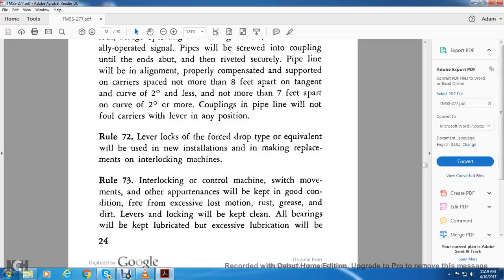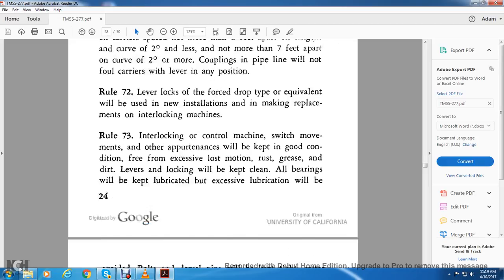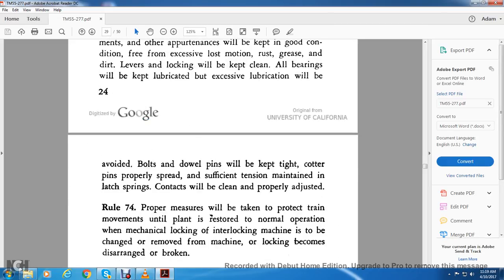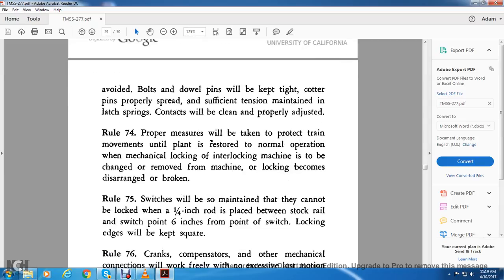Interlocking control machine switching movements and other appurtenances will be kept in good condition, free from excessive lost motion, rust, grease, and dirt. Levers and locking will be kept clean. All bearings will be kept lubricated. Excessive lubrication will be avoided. Bolts and dowel pins will be kept tight, and cotter pins properly spread. Sufficient tension will be maintained in latch springs. Contacts will be kept clean and properly adjusted.